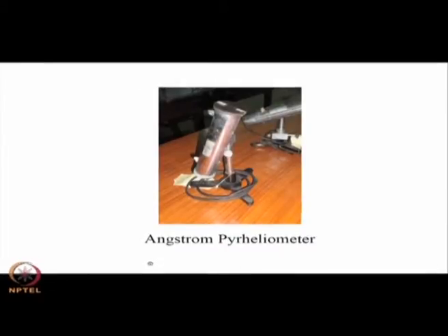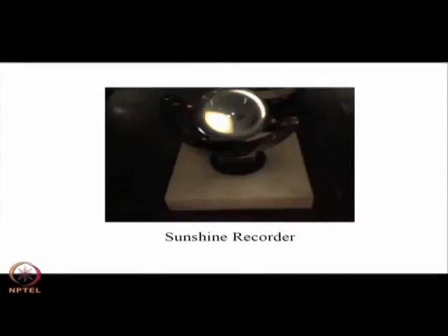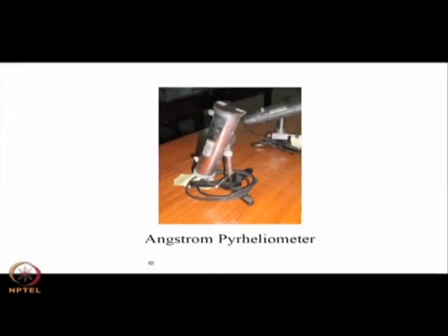This is an Angstrom pyrheliometer. The sensor mechanism is different in the sense that it uses a null detection system — similar to a post office box in electrical technology. You try to balance the system so that the current passing through a particular circuit is zero, thereby giving you a measurement of the voltage generated or the power consumed.